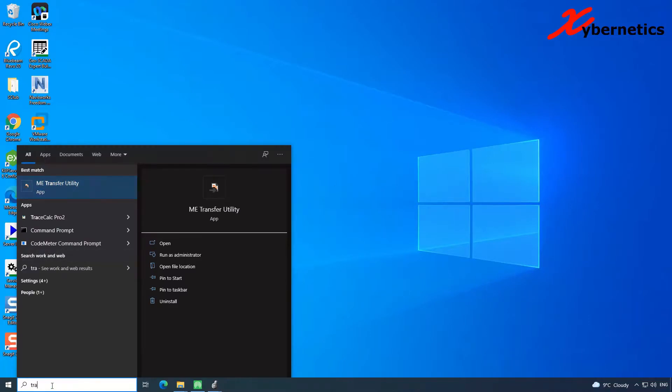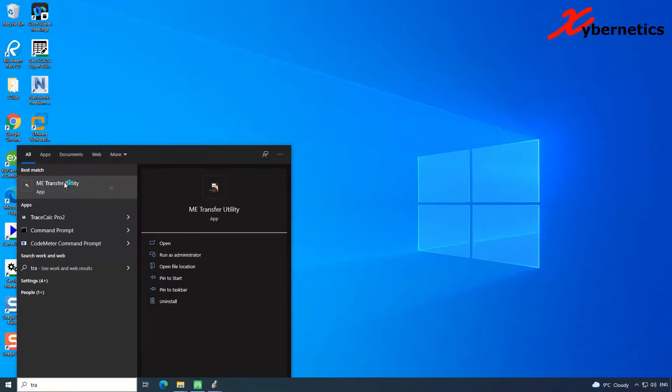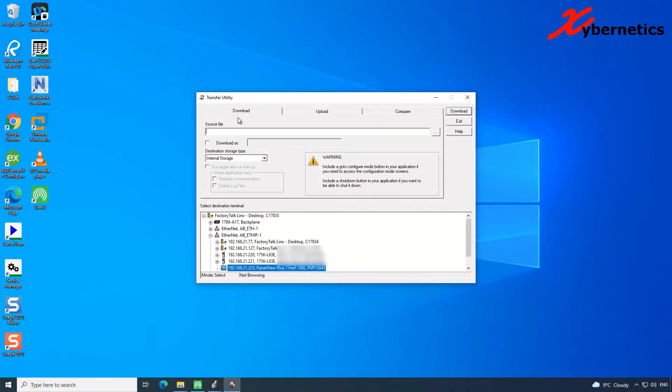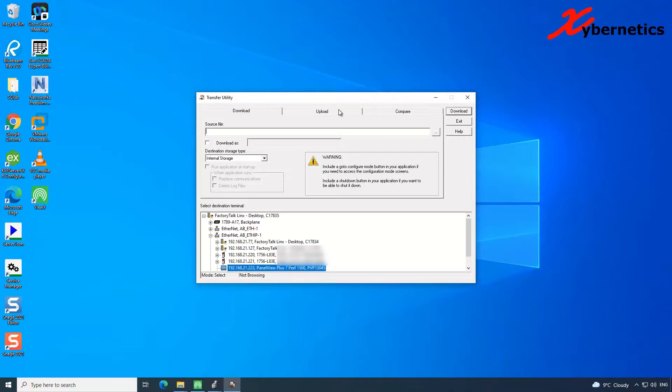Just type transfer on your Windows here. When you click on it, you'll open a pop-up window that allows you to transfer your runtime MER file. So you probably have seen this before if you have written a runtime program to your PanelView. So again, the same acronym applies. Download here, these download tabs here mean to write to the PanelView. Upload is to pull the runtime file back to your computer. Why would you want to do that? Maybe you want to keep a backup of runtime file or maybe you want to restore the runtime file into an application where you can edit using your FactoryTalk Studio.